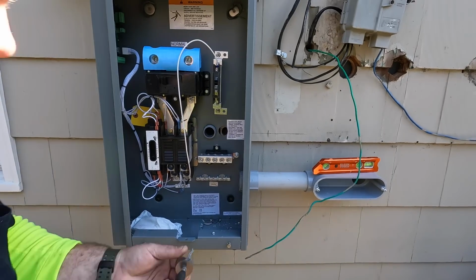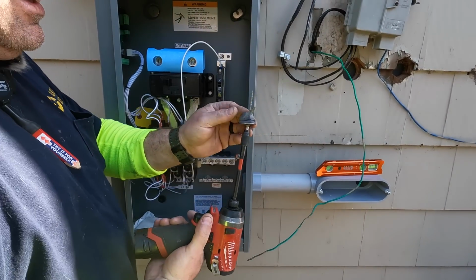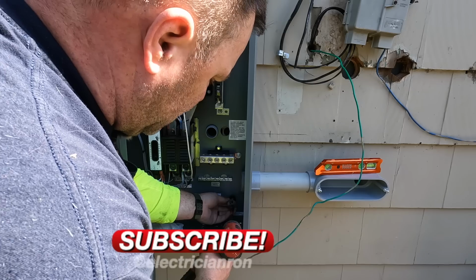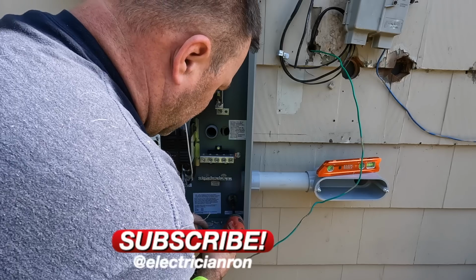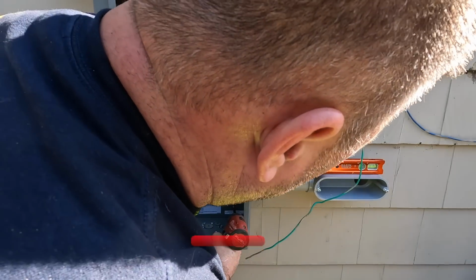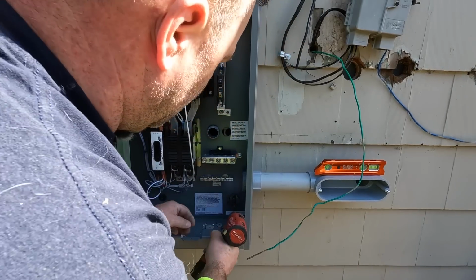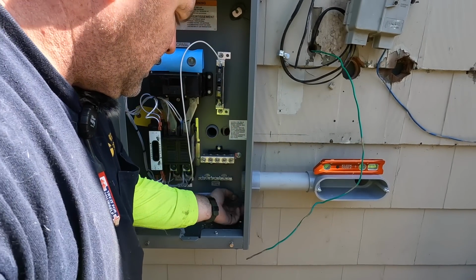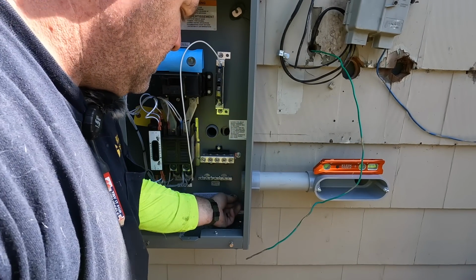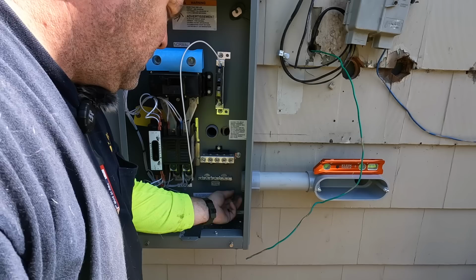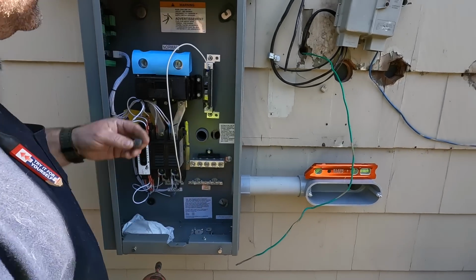See, we got the duct seal wedged in there behind the washer holding it in place. When I go to put it in here and tighten it down, you'll see it wedge in. Now that duct seal is pressed in there, it ain't going nowhere. Just take that excess off, make it look nice.